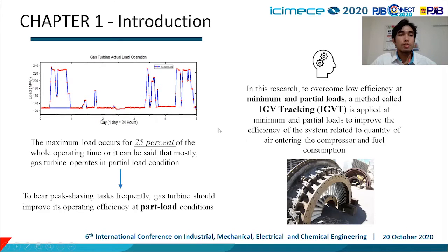In this figure, we can see that the maximum load in block number 2 Muara Karang combined cycle power plant occurs for 25% of the whole operating time. Or it can be said that mostly gas turbine operates in partial load conditions. Because peak shaving takes place frequently, gas turbine should improve its operating efficiency at partial load conditions. In this research, to overcome low efficiency at minimum and partial loads, a method called IGV tracking, or IGVT, is applied at minimum and partial loads to improve the efficiency of the system related to quantity of air entering the compressor and fuel consumption.